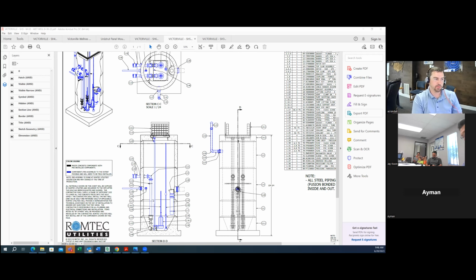So one thing we'll need at startup is a way to fill up the wet well, probably 3 to 4 times, to test the pumps and make sure everything's working. So whether that's a hydrant nearby or a tank of water, we'll need that to test drawdown on the pumps and make sure level sensing is working. Keep that in mind.